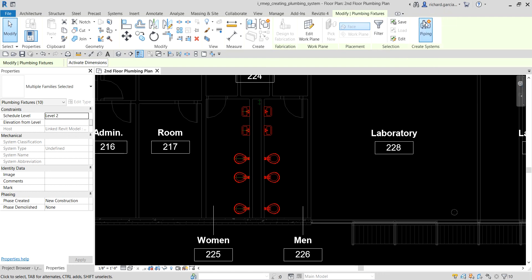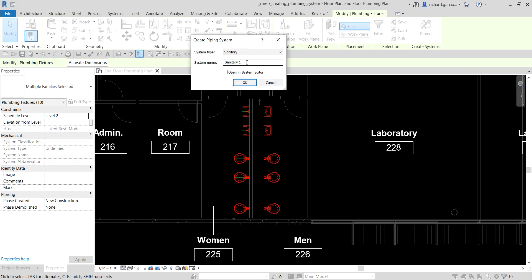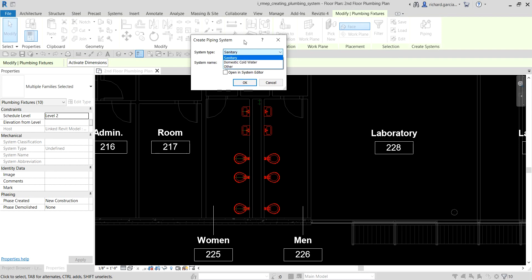Select piping, and then put the name here. We'll be creating a sanitary piping system. If you click the dropdown you can see domestic cold water and other options — it depends on the connectors you have on the plumbing fixtures. If you have hot water or other hydronic system piping connected, you'll be able to select it from the dropdown. I'll use sanitary, and change the name to 'Second Floor Sanitary,' then select OK to create the system.